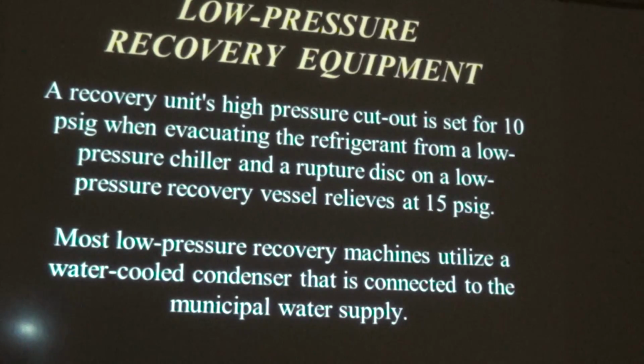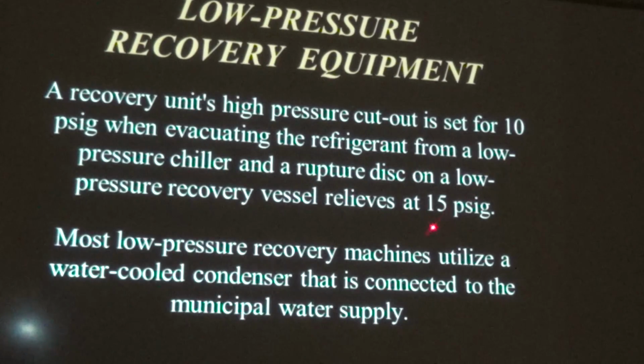Low pressure recovery equipment. A recovery unit's high pressure cutout is set for 10 psig when evacuating the refrigerant from our low pressure chiller, and a rupture disc on a low pressure recovery vessel relieves at 15 psig. Most low pressure recovery machines utilize a water cooled condenser that is connected to the municipal water supply. This whole thing, municipal water supply, believe it or not, is a test question. Why? I'll never know.